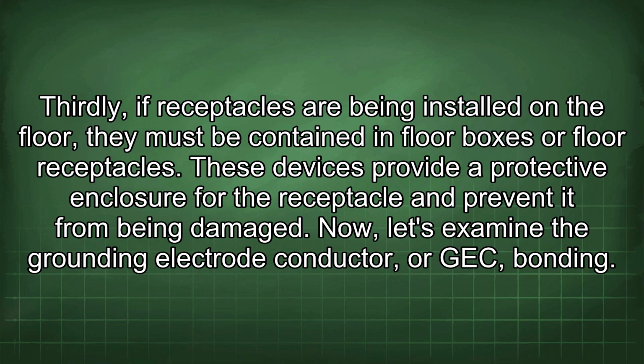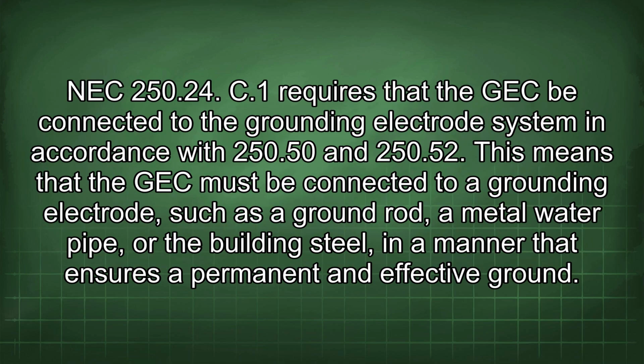Now, let's examine the grounding electrode conductor, or GEC, bonding. NEC 250.24 C1 requires that the GEC be connected to the grounding electrode system in accordance with 250.50 and 250.52. This means that the GEC must be connected to a grounding electrode, such as a ground rod, a metal water pipe, or the building steel, in a manner that ensures a permanent and effective ground.